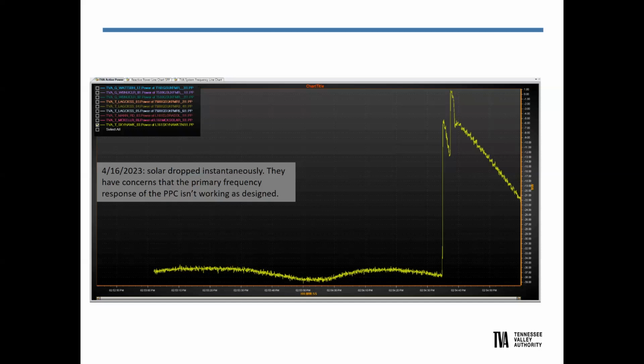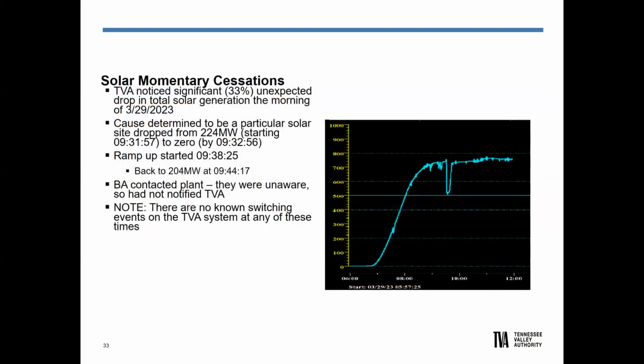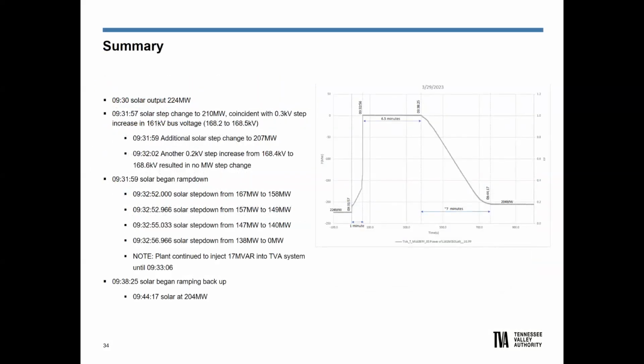The next set of slides here, if you go to the next slide, is that we saw some additional momentary cessation. Again, we have about 700-800 megawatts of solar installed right now. This spring, we saw about a third of it drop out. We figured out, if you go to the next slide, it was a particular plant. It was about 224 megawatts. We saw a voltage change as well as the 200 megawatt dropout at the time. You can see all the different recoveries here.